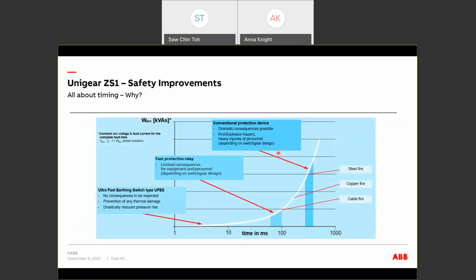So what we discussed so far in the previous slide is passive protection. We include internal arc tested panels, remote racking and remote earthing. These are all passive protection. But for customers looking for extra safety, we can also look at active protection. So this chart shows a typical energy against time chart in the event of an internal arc.